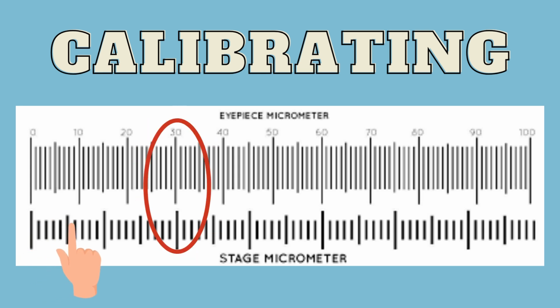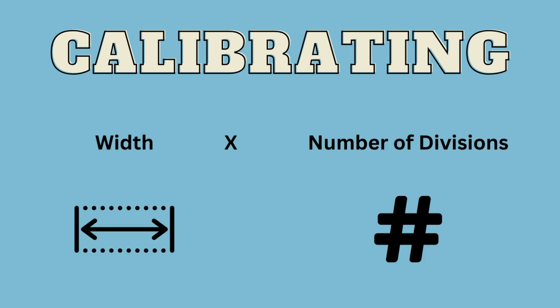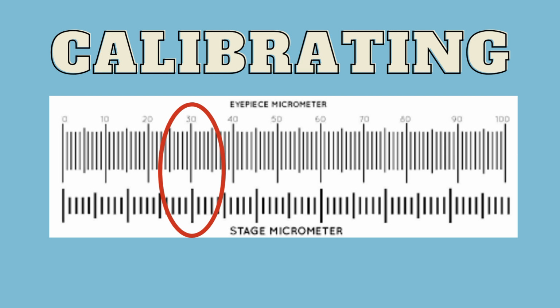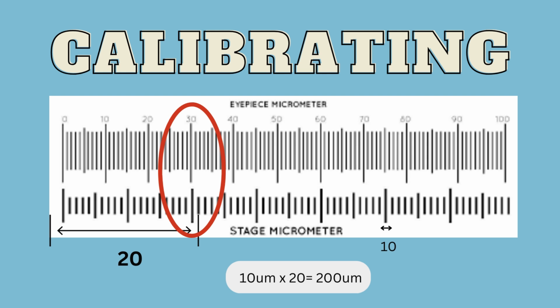Then, count how many divisions of the micrometer are present up until that point. Then, calculate the width of the stage micrometer lines and multiply that number by the amount of divisions. For example, in this image, the reticle and micrometer align at 30, and there are 20 divisions before that point. The width of the stage micrometer line is 10 micrometers. So, 10 micrometers times 20 divisions is equal to 200 micrometers.